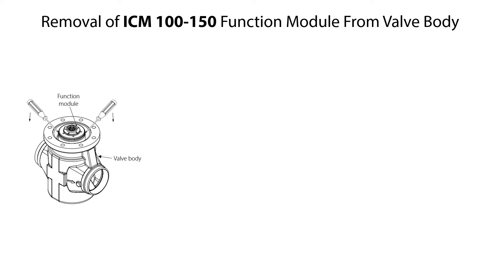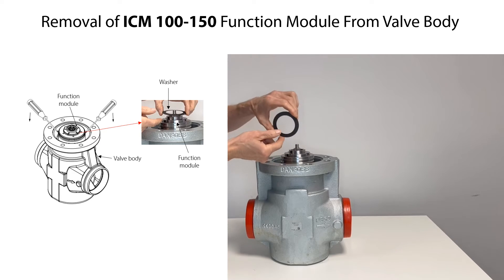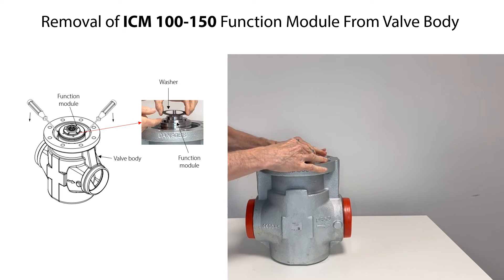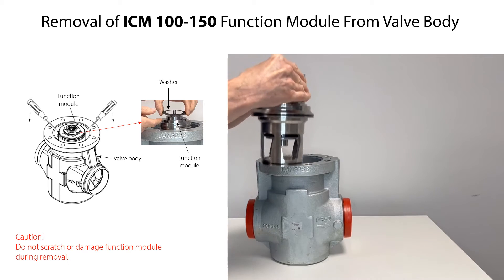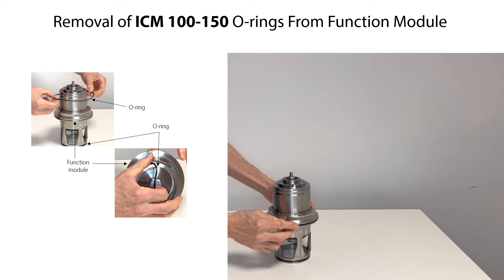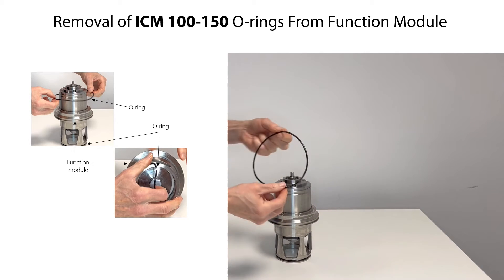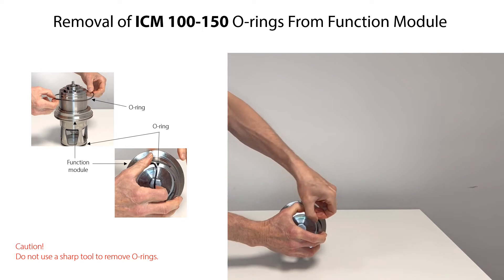To remove the function module from the valve body, firstly remove the washer from the top of the function module. Then insert two screwdrivers in the machined groove on the outside of the function module and tilt the screwdrivers to loosen the function module and its o-rings from the valve body. Carefully lift and remove the function module — be careful not to scratch or damage it during removal. Carefully remove the o-rings by hand from the function module and replace them if needed. Do not use a sharp tool to remove the o-rings since this might damage the o-ring grooves.